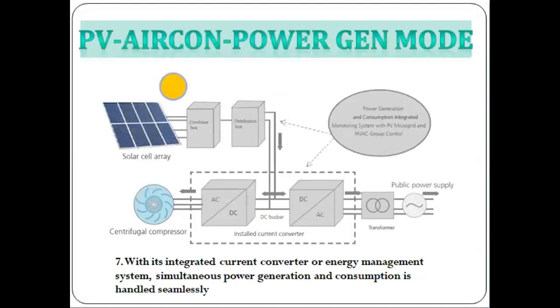Number 7, with its integrated current converter or energy management system, simultaneous power generation and consumption is handled seamlessly within 10 milliseconds. In this mode, some of the power supplied by the PV system is used for GREE PV chiller units operation, while the excess power is supplied to the power line. The installed integrated monitoring system will display the PV-AIRCON-POWER gen mode when power generated by the photovoltaic system exceeds the requirements of the GREE chiller, and this can happen during part load performance of the chiller.